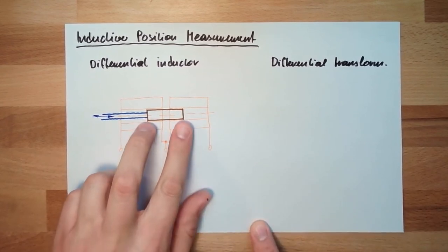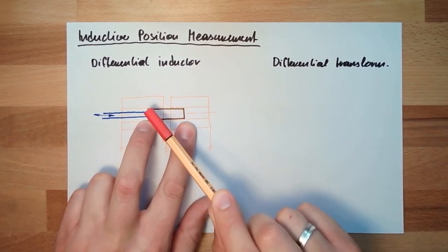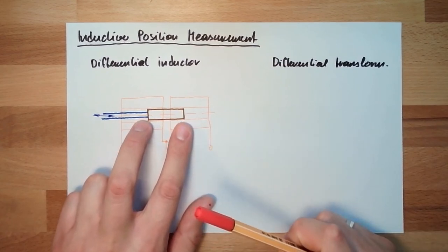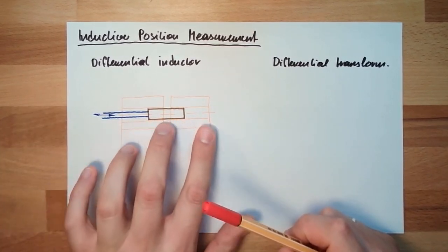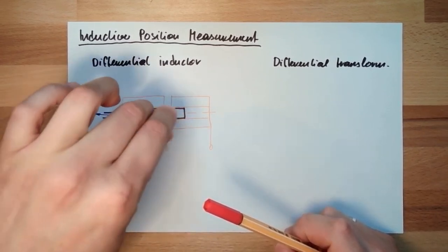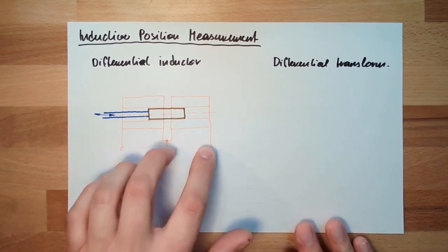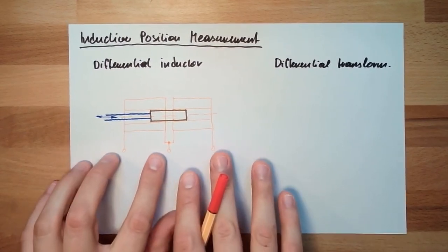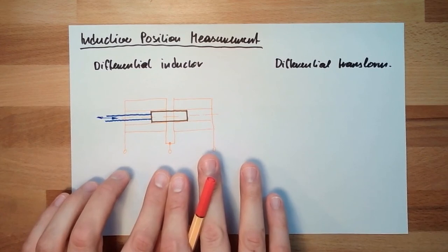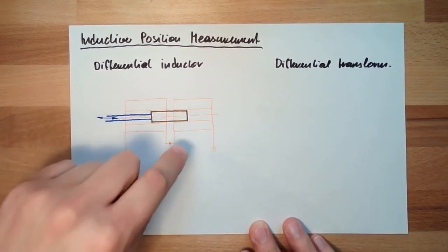This means if I am moving this from its middle position, this one will lose inductivity and this one will gain inductivity. So if I am moving in this direction, this one gets higher inductivity and this one gets less inductivity. If I am moving in the other direction, the opposite is true — this one gets less inductivity and this one gets higher inductivity. And this inductivity can be measured. I measure the inductivity here and here, and from the difference of the two inductivities — that's why it's called differential inductor — I can determine the position of this ferromagnetic part.